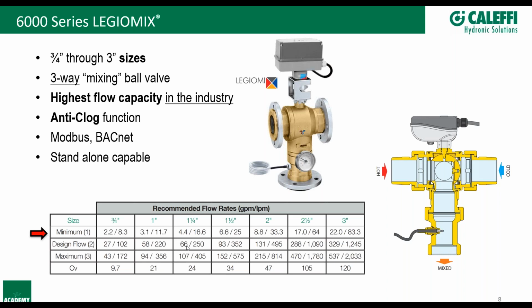And that minimum flow requirement is there to make sure that you maintain velocity in the body of the mixing valve and maintain a good turbulent mixture in there so the sensor doesn't see all hot or see all cold. And that way it can regulate temperature very, very well. So again, really high flow rates, really low pressure drops. You'll notice that we have all of this published in our literature as far as minimum flows, design flows, maximums. Now, minimum flow requirements, don't be terribly afraid of these, because if you are running constant recirc, which we're always going to recommend to prevent stagnant water, again, the idea of growing more and more Legionella bacteria, if you do meet minimum flow requirements with your recirc, then you're not going to have any issues with temperature stability coming out of the mixing valve, which is great.